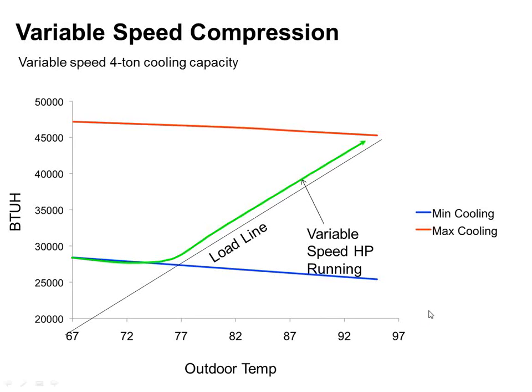On the cooling side, having that load matching ability to track the load line gives me significantly better dehumidification than cycling a system on and off. Hence, I get better comfort. If I want to do zone dampers on there, I can do that and be able to turn down to lower rates. Everything just works out better for me. There are some components that are going to be different in a variable speed heat pump versus a regular heat pump, versus even an air conditioner.